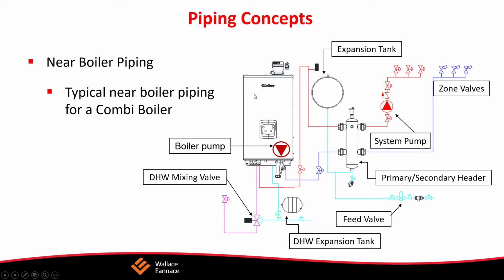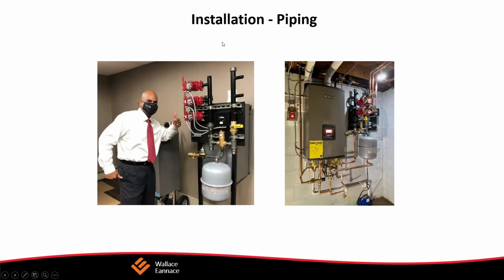Here's what we should be doing now. As you can see, we have an air elimination device. Over here, we have our expansion tank, and the pumps are pumping away from the expansion tank. Also, we have our indirect hot water heater and check valves to make sure that we don't get ghost flow into the other zones. So we have a number of ways that we can pipe.